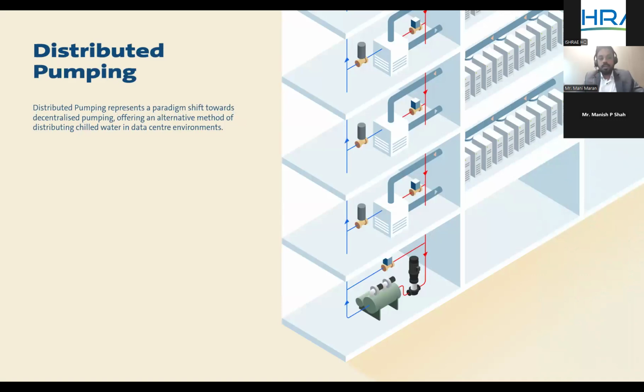Let's see what distributed pumping is. Distributed pumping is basically a shift towards decentralizing the pumps. In the traditional way of pumping, we have a centralized pumping system and we distribute the water across the network. As the name implies, in distributed pumping we assign a pump to address the need of each load. So no more centralized pump. We are decentralizing the pumps to each node to address the need of that node in a better way. This is an alternate method to what we are doing today to distribute chilled water in a data center environment.